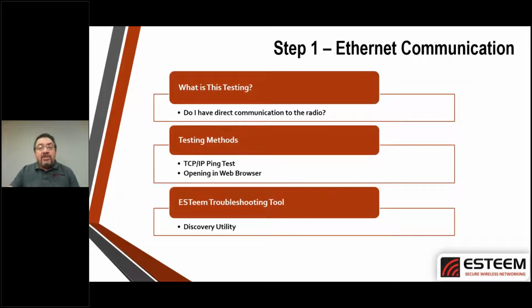The first step really is Ethernet communication. In other words, can we talk to the radio? Seems pretty simple, so what are we actually testing? We're testing to see if our computer and the radio are able to work together. In other words, is the Ethernet port on the radio still functioning? It's very possible that it's been damaged or something has gotten in there. Of course, we can be dealing with cables and all the rest too, but are we able to talk to it within the network?